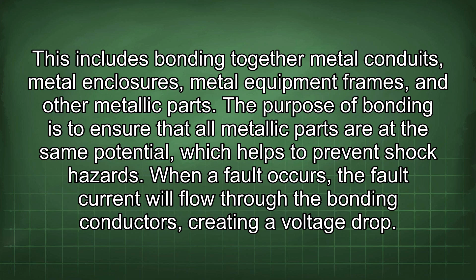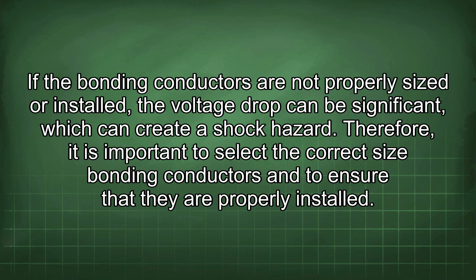If the bonding conductors are not properly sized or installed, the voltage drop can be significant, which can create a shock hazard. Therefore, it is important to select the correct size bonding conductors and to ensure that they are properly installed. The National Electrical Code provides specific requirements for bonding, including the size and type of bonding conductors, as well as the methods for connecting them.